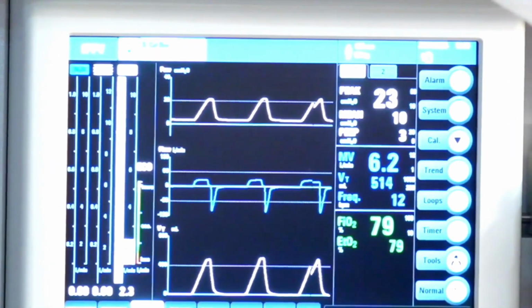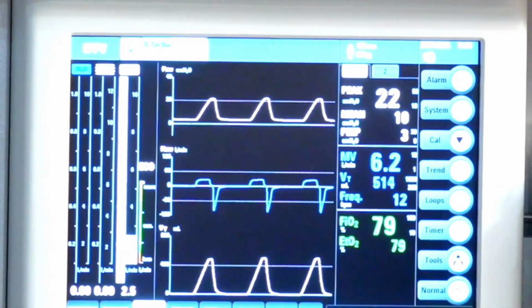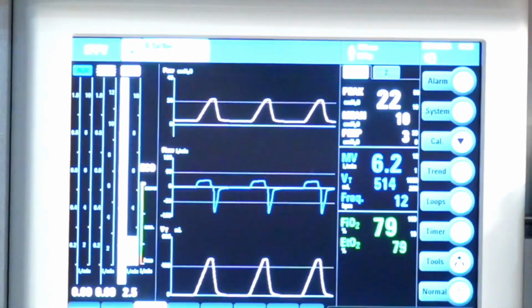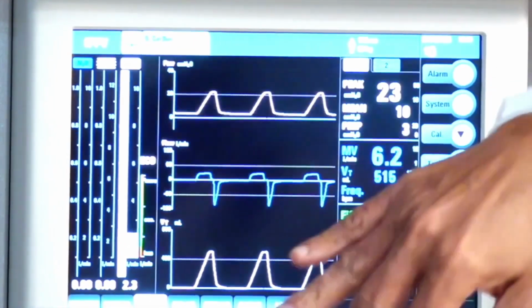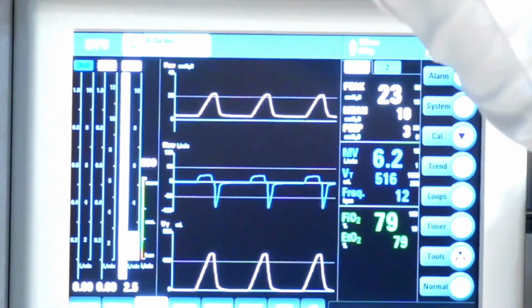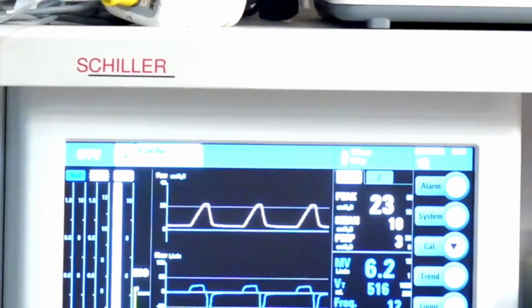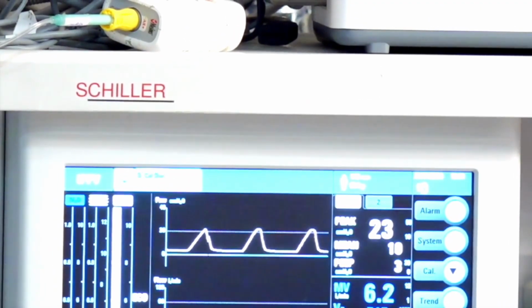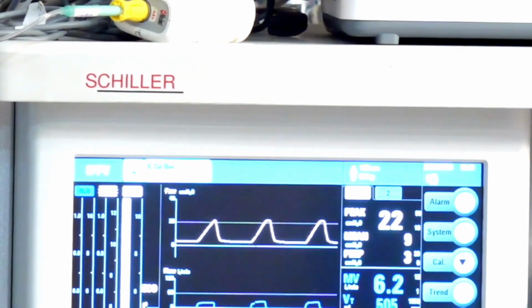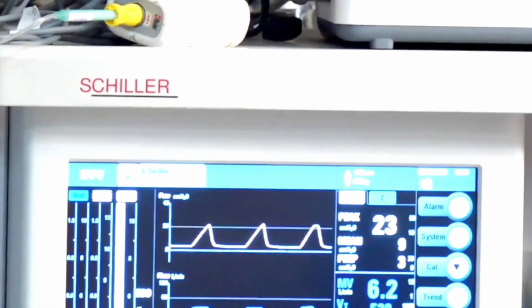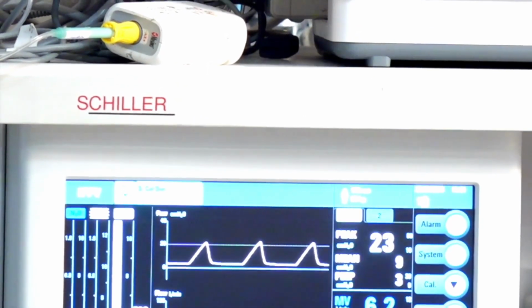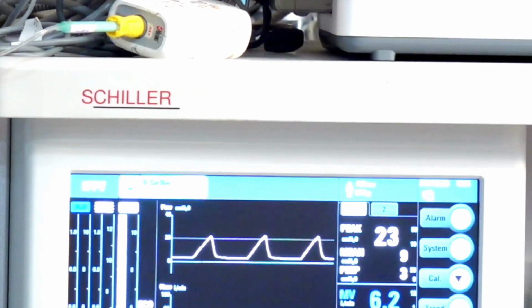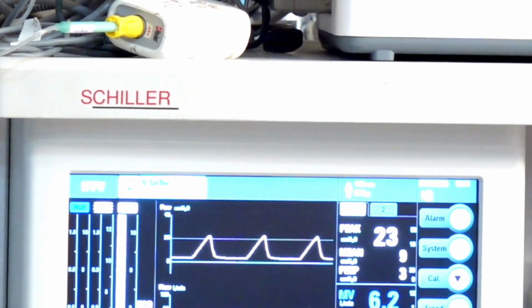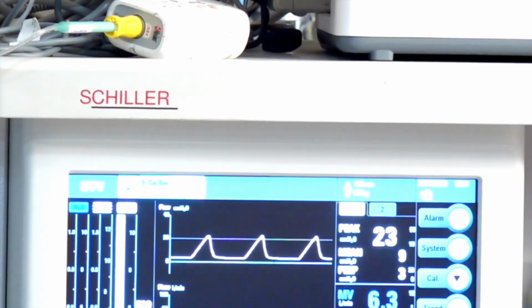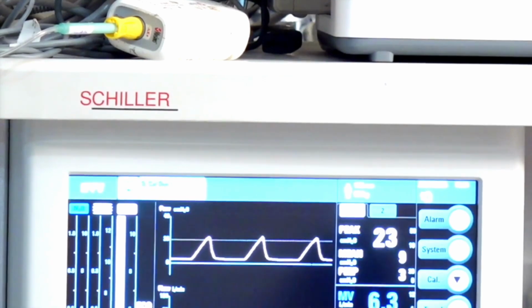Okay. Now here the graph is nearly flat. But otherwise, it should go to the peak, settle down to a slightly different value, which is your Plateau pressure, and then it should come down. If you remove this Plateau, the top flat part will go away. It has become sharp. So to get Plateau pressure, which we really want for the driving pressure and lung protective ventilation, you need to apply a pause, which is not a default value in most of the machines. So you need to really add it to get the Plateau pressure.